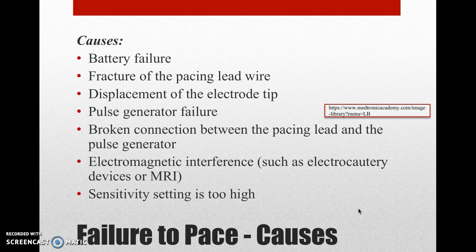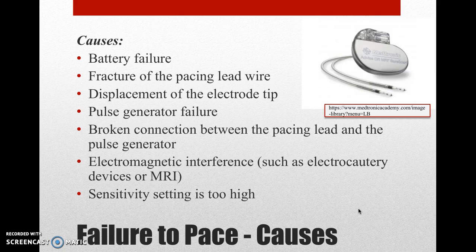Failure to pace has different causes such as battery failure, fracture of the pacing lead wire, displacement of the electrode tip, pulse generator failure, a broken connection between the pacing lead and the pulse generator, or electromagnetic interference such as electrocautery devices in the OR or MRI, or if the sensitivity setting is too high.